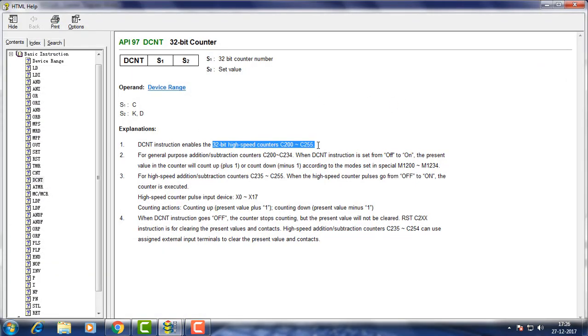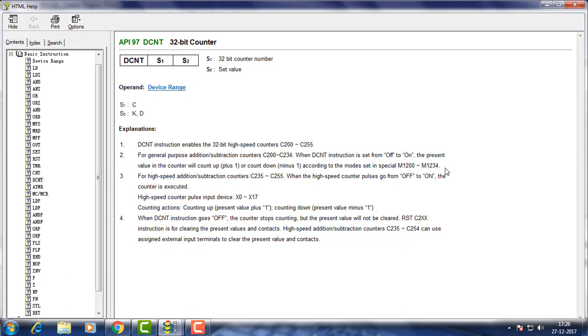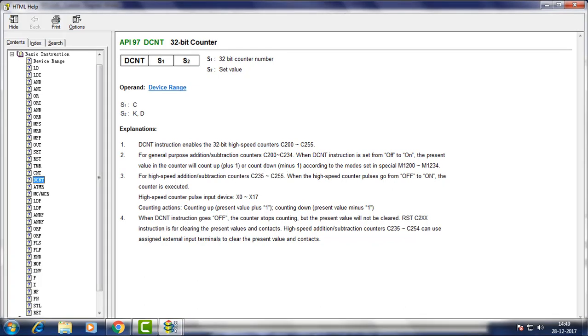Counters numbered from 200 to 255 can only be used in this counter. Counter number is chosen according to purpose as it is explained here. Counting up or down is decided by the status of corresponding memory from M1200 to M1234.